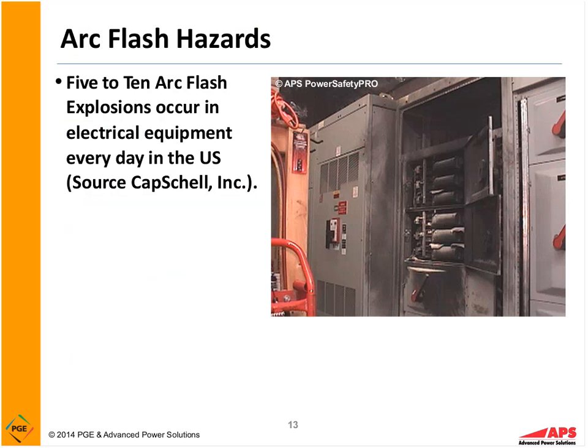Now, when we look at this, we say, well, the door was closed. How could he receive injury? Because the electrical gear is not always rated to contain the arc. In fact, it is not rated. It is not tested to contain an arc. In some cases where we have low energy levels, it may contain the arc. In other cases, it may not. This was a 600-amp fusible disconnect, but it was on the upstream side of that fuse. It was a 1,200-amp switchboard, and it had almost 50,000 amps of fault current, which meant it had a lot of energy that it had to release when a fault occurred, okay, and that was released. So, again, we can see electrical explosions occur.